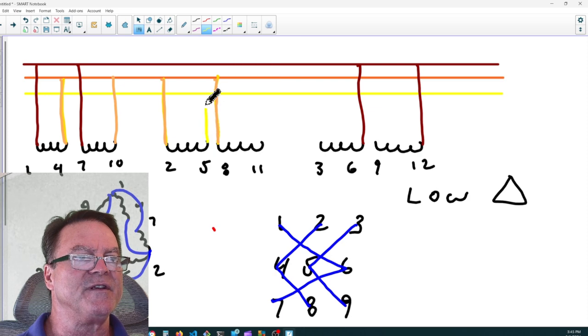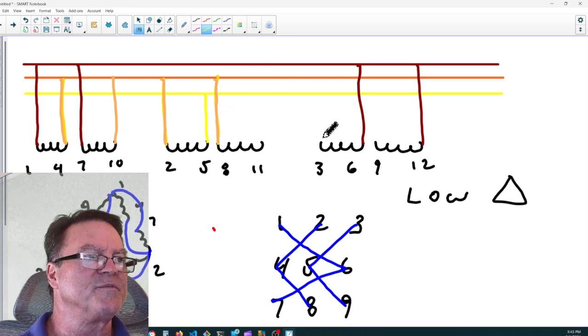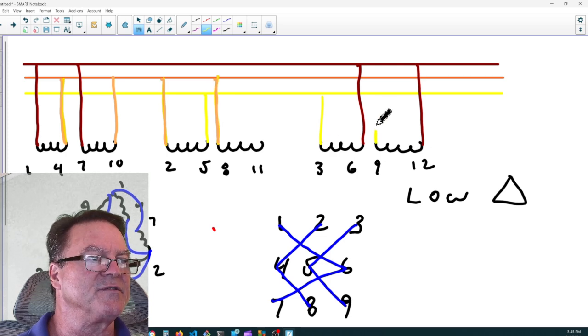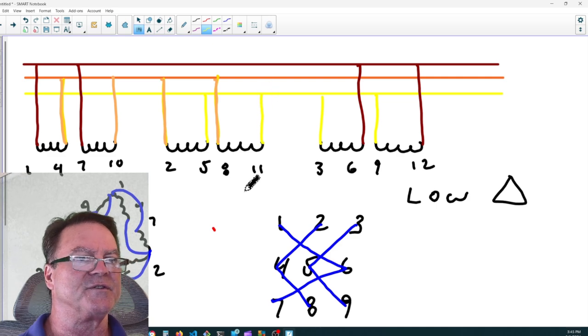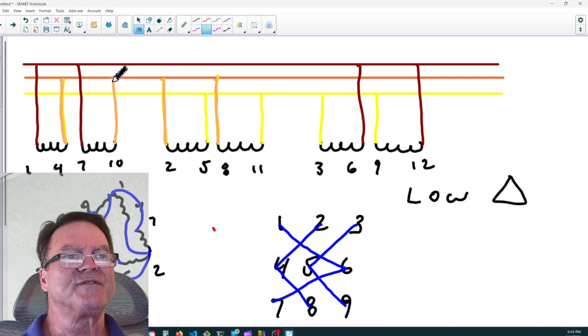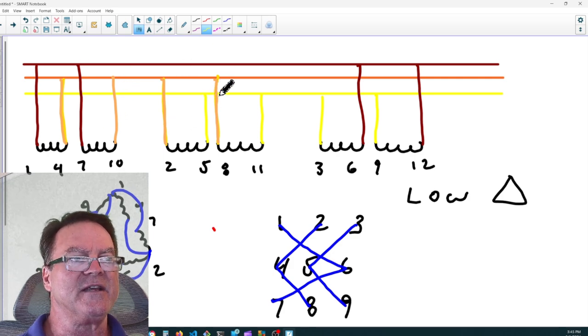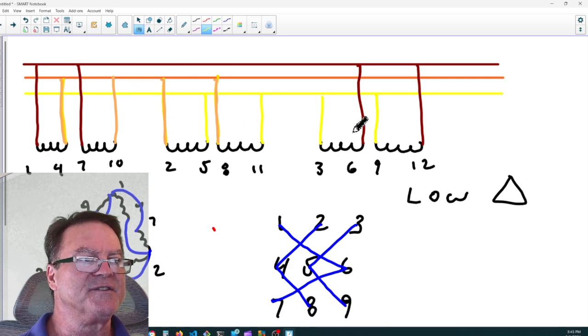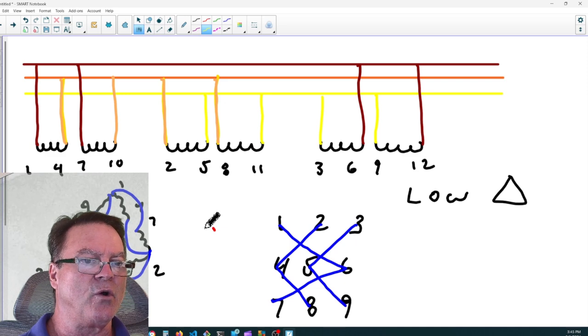So 3 goes to C phase. Oops, wrong one, sorry. 3 goes to C phase, 5 goes to C phase, 9 goes to C phase, and 11 and 3 are tied together, so it also goes to C phase. So now it's very easy to see A to B, A to B. Those are in parallel. B to C, B to C. Those are in parallel. C to A, C to A. Those are in parallel. Okay, so there's your delta low.